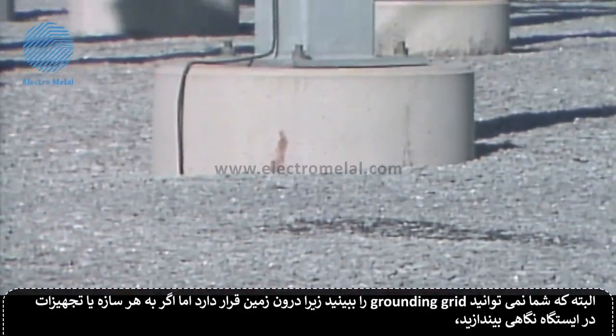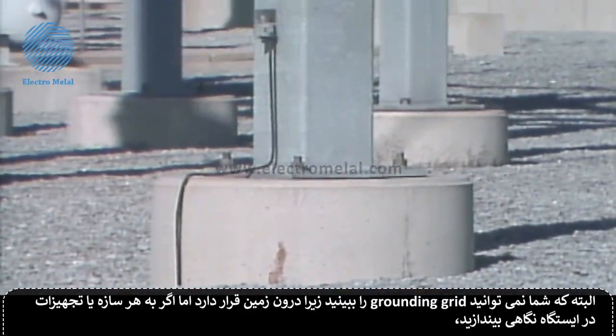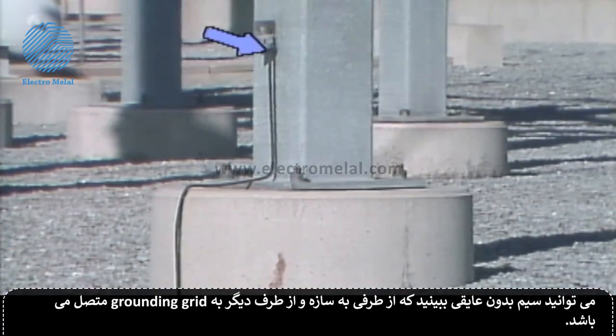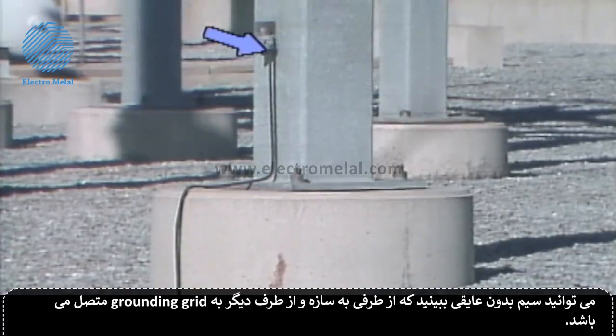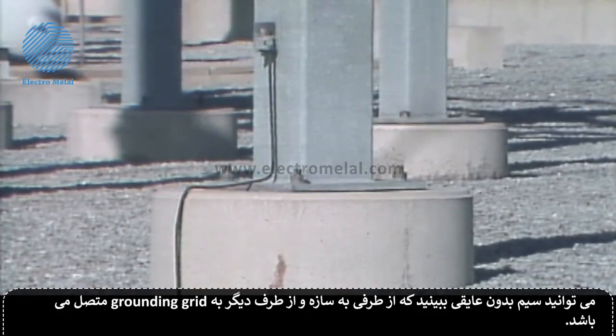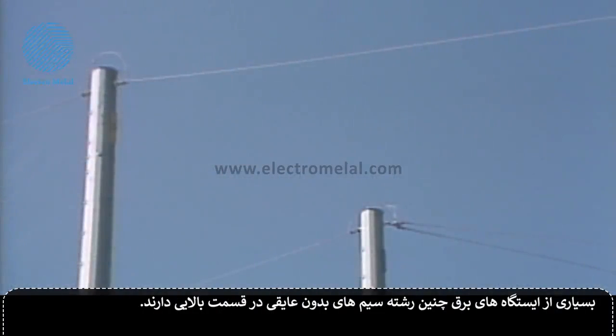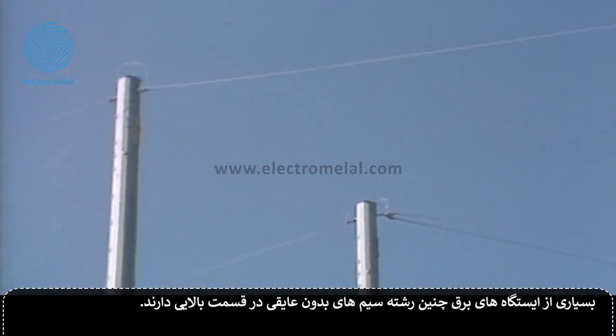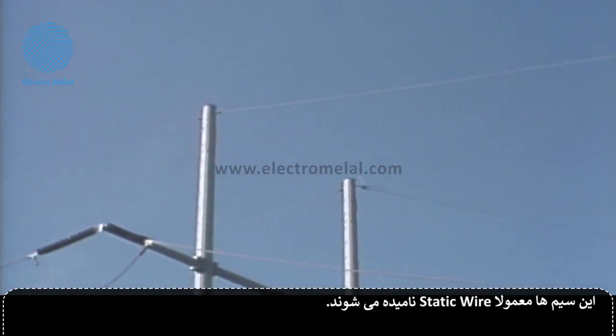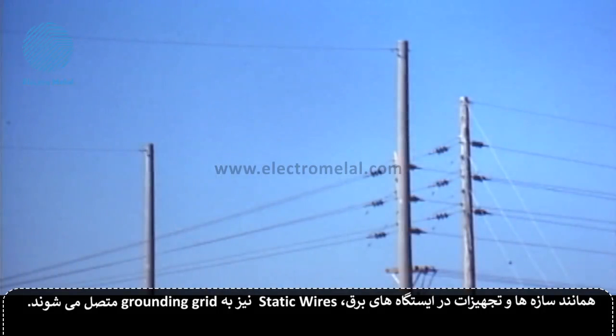But if you look at each of the structures and equipment in a substation, you'll find bare cable connected to them that runs down into the ground. Each cable connects to the grounding grid. Many substations also have bare wires that are strung above it. These wires are commonly called static wires. Like the structures and equipment in the substation, the static wires are connected to the grounding grid.